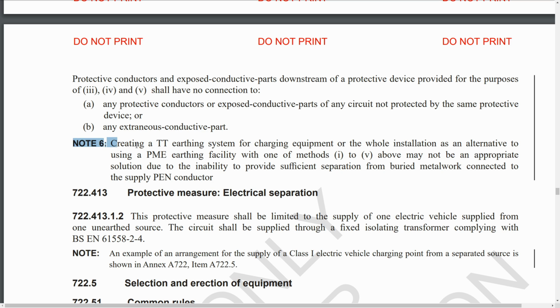Note 6 is of particular importance here. Creating a TT earthing system for charging equipment or the whole installation as an alternative to using a PME earthing facility with one of the methods above may not be an appropriate solution. Now, this is where you've got the TNCS or PME supply, and rather than going through all those things we just mentioned, you can simply not bother to use the PME terminal whatsoever, just not connect to it at all, install your own electrode or electrodes in the ground, and then make it a TT installation. Now this is not necessarily appropriate because due to the inability to provide sufficient separation from buried metalwork connected to the supply PEN conductor.